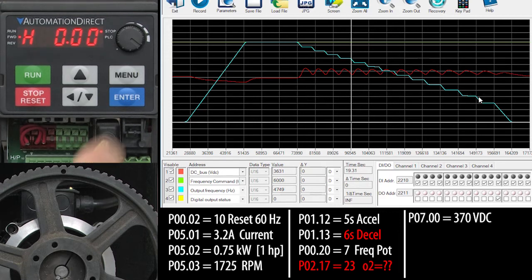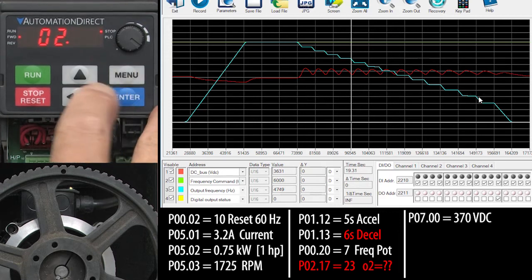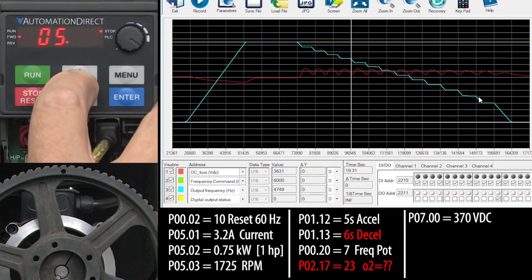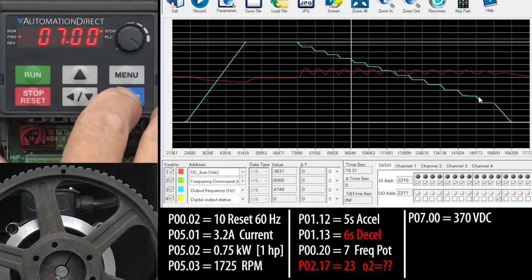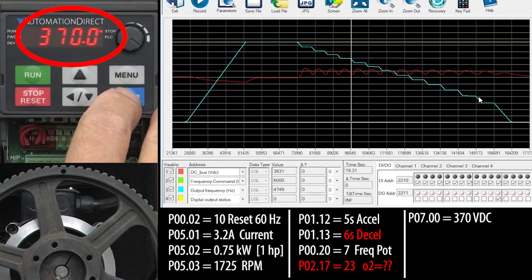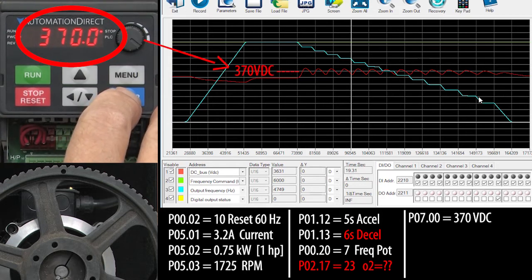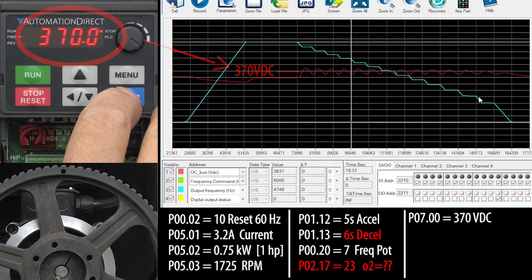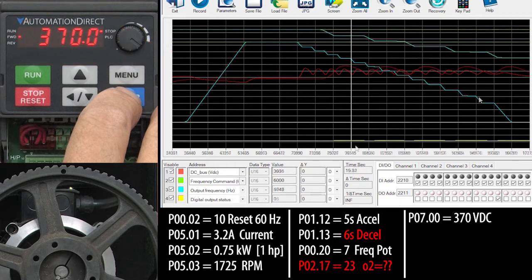You can change the voltage level this trips at in parameter 7.0. And look at that, the default is 370 volts – exactly what we saw. I wouldn't mess with that unless you really know what you are doing. Just know that it's there if you want it.